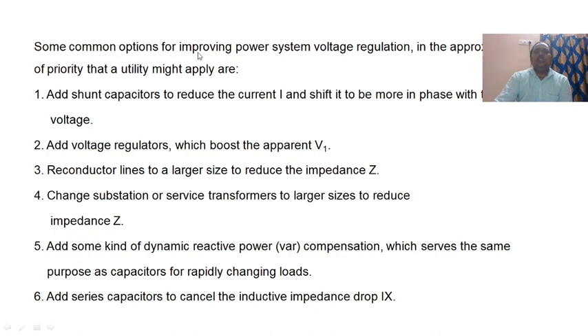Some common options for improving power system voltage regulation, in the approximate order of priority that a utility might apply, are as follows. First, to decrease sags, add shunt capacitors to reduce the current I. Add shunt capacitors to shift the current to be more in phase with the voltage. Second, add voltage regulators which boost the apparent V. Reconductor lines to a larger size to reduce the impedance Z. Change substation or service transformers to larger sizes to reduce impedance Z.